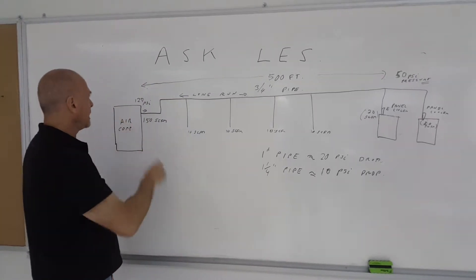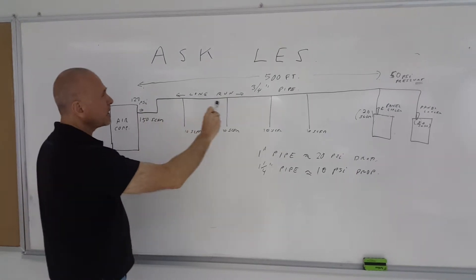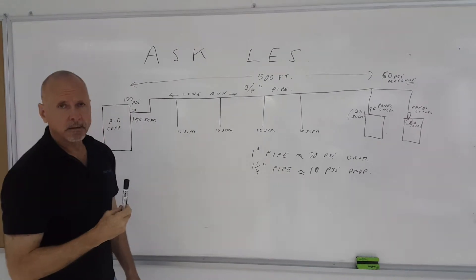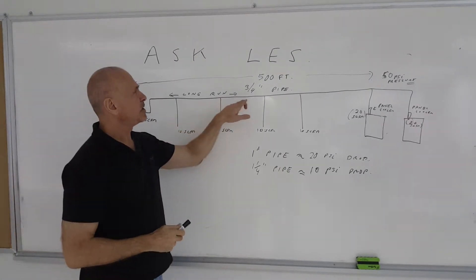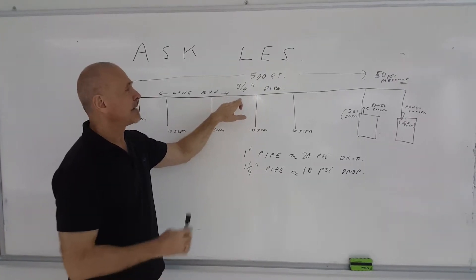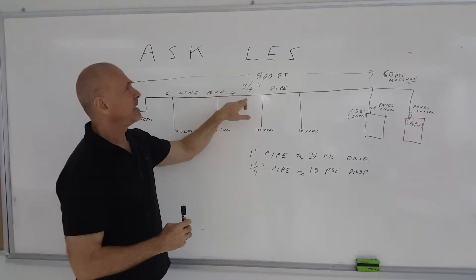Well, we found out that they were utilizing only three-quarter inch pipe to deliver the compressed air throughout their whole factory. They had enough compressed air, but the pipe size was just too small to have it utilized efficiently, or utilize that much compressed air at that end efficiently.